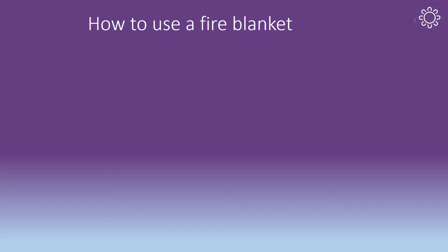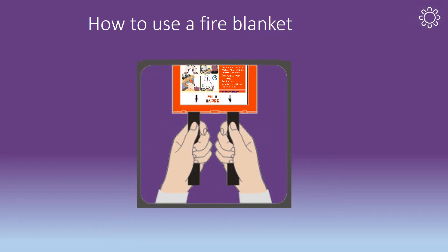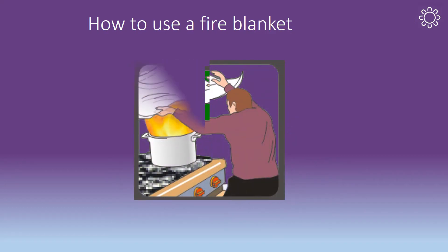To use the fire blanket, you will first need to remove it from its wall mounted holder by pulling the two tabs at the bottom. Unfold the blanket so it is completely opened. Hold the fire blanket with your hands wrapped in the top edge of the blanket — this will protect your hands from the heat and flames. Cover the flames completely with the fire blanket by throwing or placing the blanket on top of the fire and leaving it there until the fire goes out.